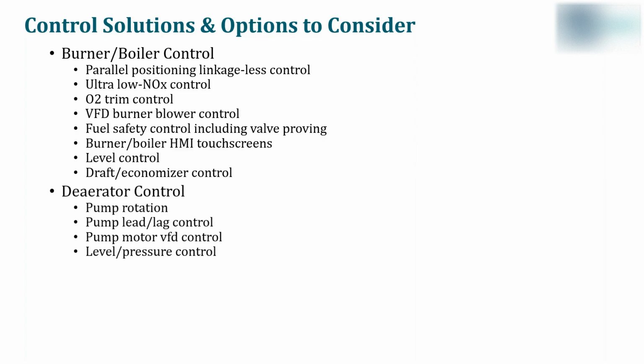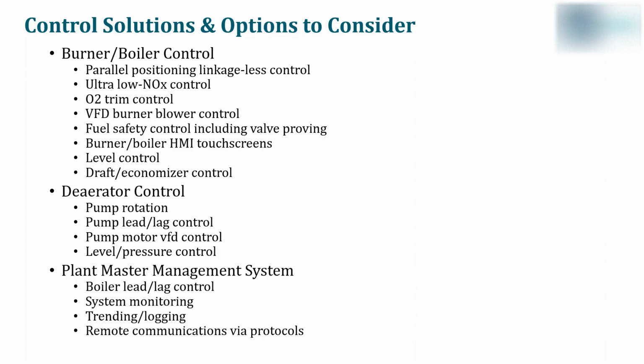For deaerator control, it's pump rotation, pump lead lag control, pump motor VFD control, and finally level and pressure control. And finally, to tie all this equipment together, the plant master management system. This would include the boiler lead lag control, system monitoring, trending, logging, and remote communications via protocols. Now, the DA and the plant master are topics that we will not be covering today. These have already been covered in great detail by my colleagues in previous webinars, and at the conclusion of this webinar, you'll be provided with a link to our YouTube channel to view these.